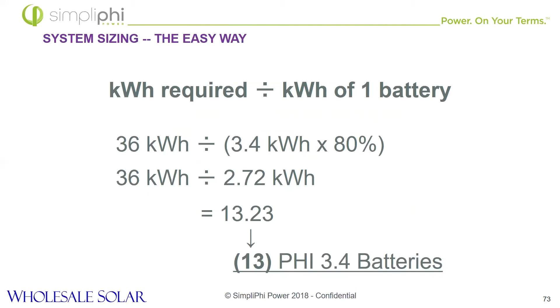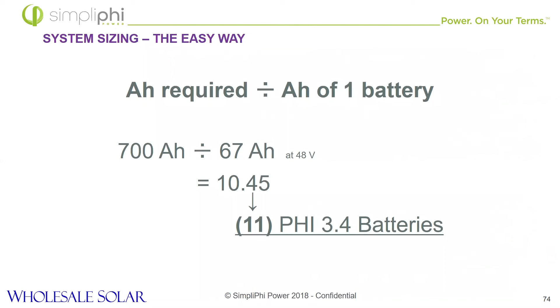Especially for everyone familiar with lead acid from the lead acid days, they're normally designated by amp hourage. You can do that same calculation, and take 80% of the 67 amp hours per 48 volt battery. For those keeping score at home, 80% of 67 is 53.6. So you'd divide 700 by 53.6, and that tells you how many batteries you should use. So those are some simple calculations you can do with a calculator.